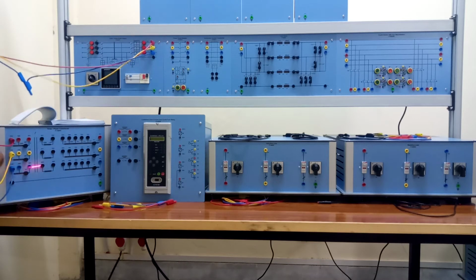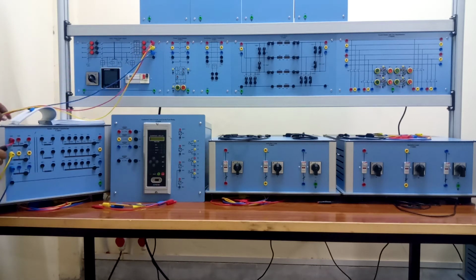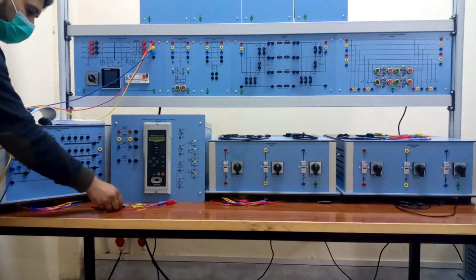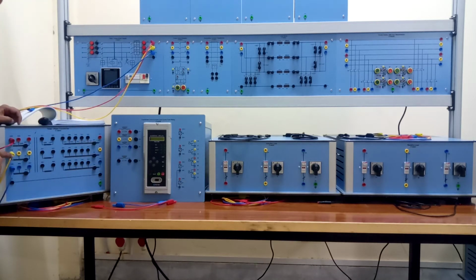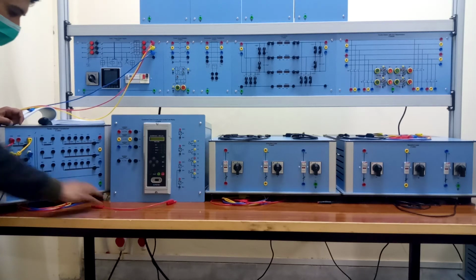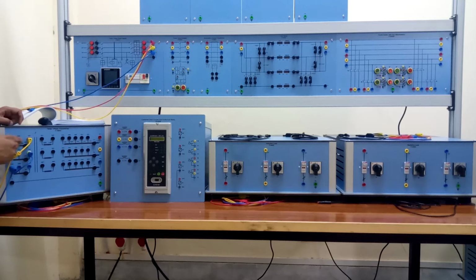The next step is to connect these 3 phases in delta. For delta connection, it's very simple: you connect the yellow phase to the red phase, the blue phase to the yellow phase, and then the red phase will be connected all the way to the blue phase. This makes a delta connection.